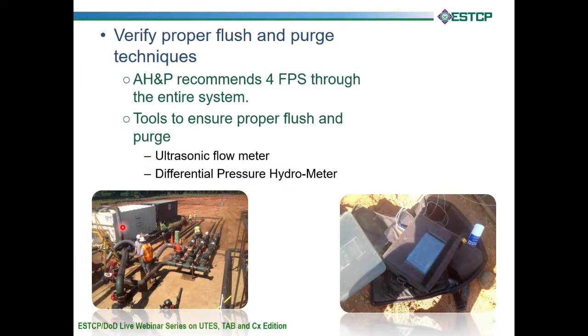I actually think it's out of the picture. I think this is actually a storage container here, but there's a frac tank over here and a pump. The pump pulls water out of the frac tank, circulates it through the system at a minimum of 4 feet per second, dumps it back into the top of the frac tank where all the beer cans and cigarette butts and air bubbles and everything else that got left in there was separated. And so we were there for all of that, and we made sure all that happened correctly.